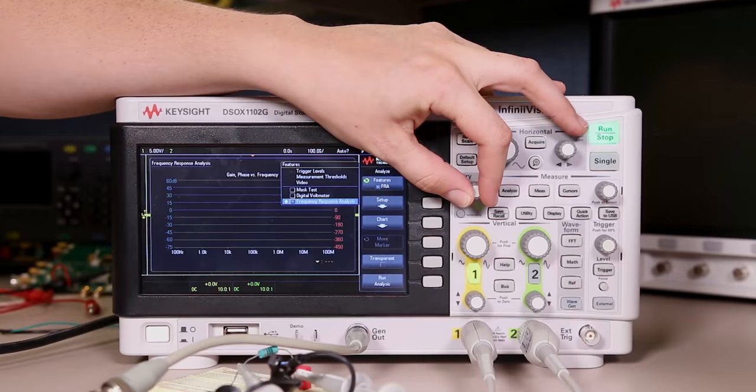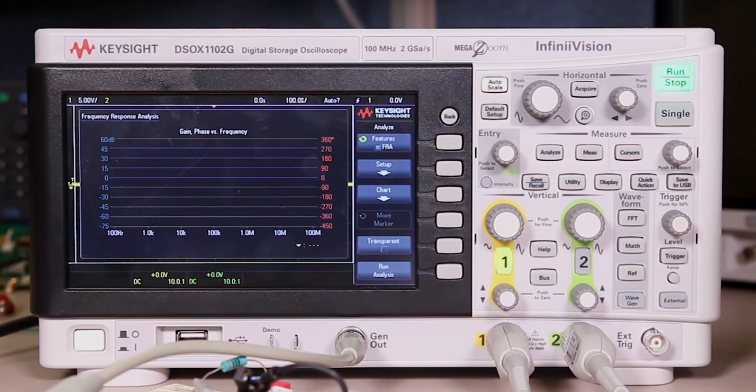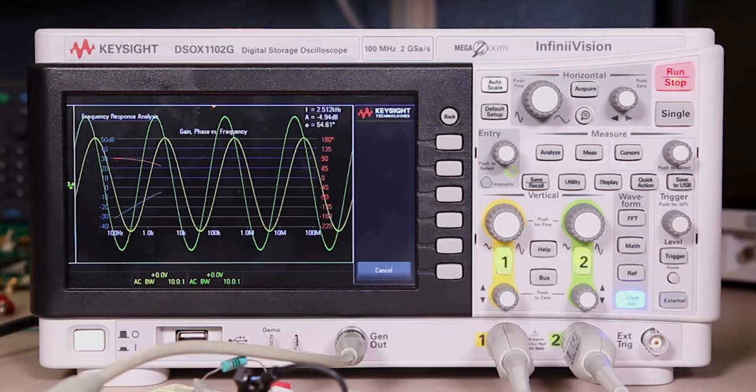The frequency response analysis application is also available on the low price 1000x series oscilloscope. So this is a lot of performance to get in this little scope. The features of the application are a little bit more limited. For example you can't set the custom amplitude profile but it gives you the gain and phase data in the form of a Bode plot on the screen so you're able to make these types of measurements on this class of an oscilloscope.